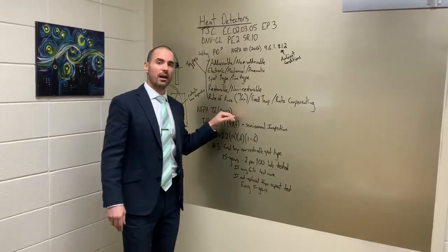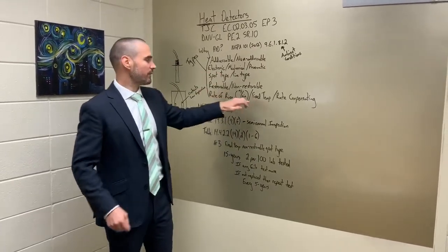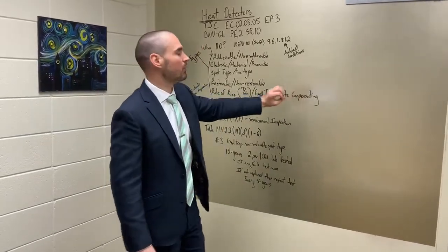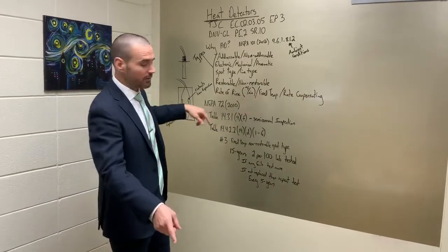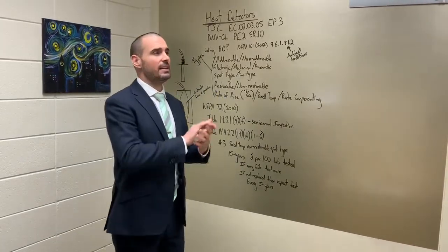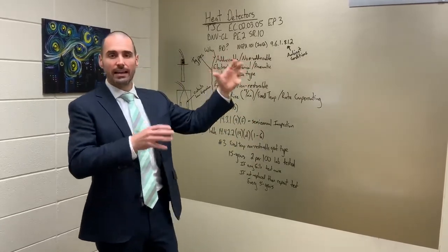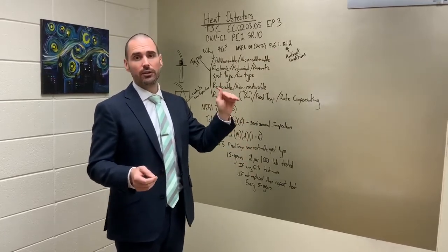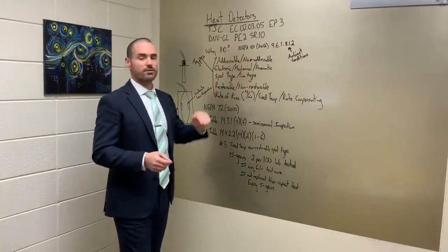There's several different types of detectors from how they activate. Rate of rise, fixed temperature, and rate compensating. You're not going to find as many rate compensating, but we'll still talk about them. You can also have combination rate of rise, fixed temperature, which we do have an example of. Rate of rise simply means when the ambient temperature raises a certain amount in a given set period of time, it's going to trigger an alarm. The most common is 15 degrees in one minute. So if the temperature goes up 15 degrees within one minute, it triggers an alarm.